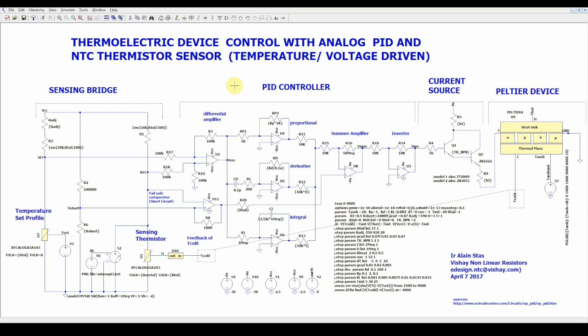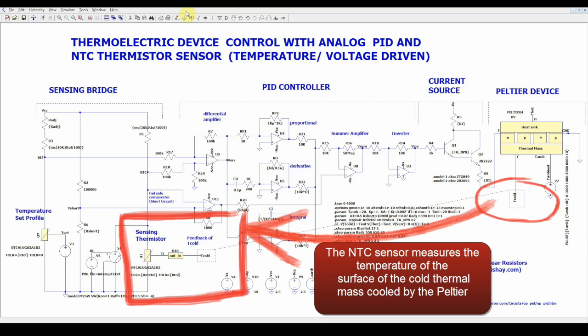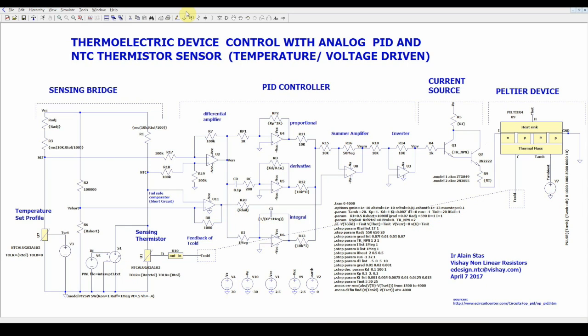As a PID input, we have the voltage of the Wheatstone bridge comparing the voltage of the NTC sensor at its temperature and the equivalent voltage of the setting temperature profile.